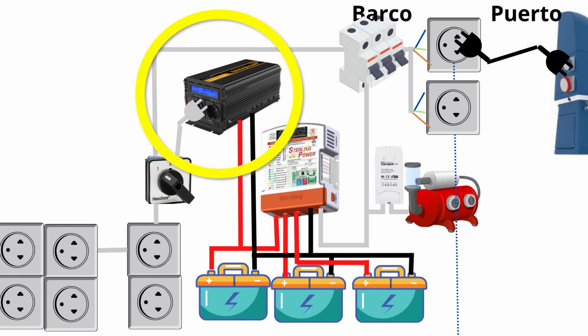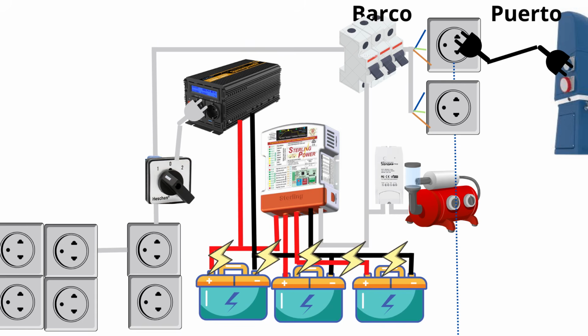For me, the best way to install an inverter is by integrating it into the same AC system you already use with shore power. In my case, I added the inverter following a wiring diagram like this. The inverter needs to be located very close to the batteries that supply it, because a lot of current can flow through the DC cables as soon as the power we're using increases even slightly, and otherwise you'd have to use extremely thick cables, so it's really not worth it.